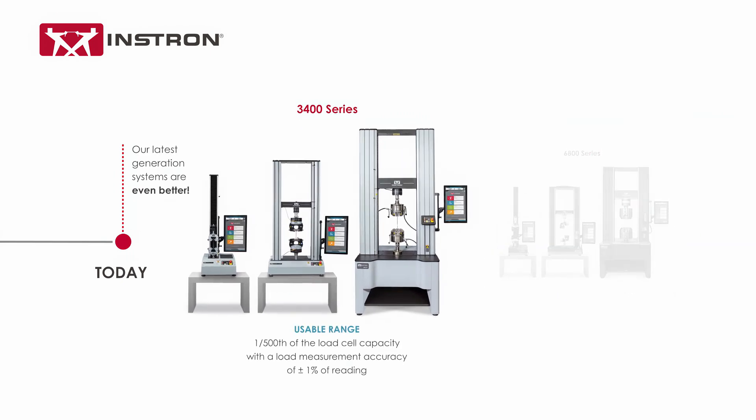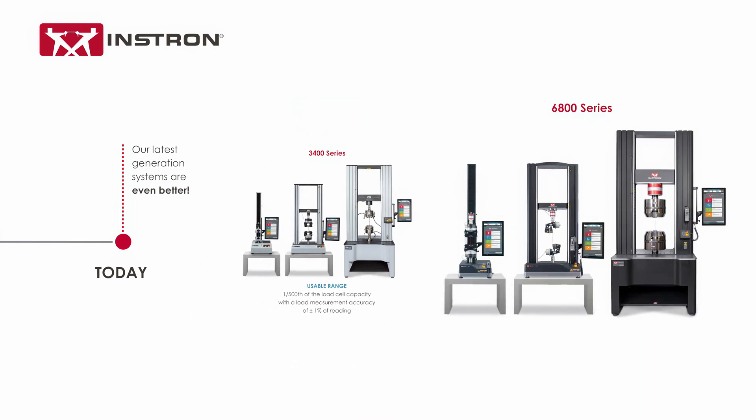The usable range of our 3400 series universal testing systems are equipped to measure one-five-hundredth of the load cell capacity with a load measurement accuracy of plus or minus one percent of reading, while the 6800 series can measure down to one one-thousandth of the load cell capacity with a measurement accuracy of plus or minus 0.5 percent of the reading.